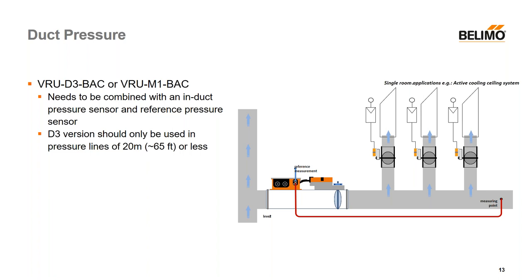A nice thing about duct pressure control is that if you have a corridor with many identical or similar rooms downstream, controlling the pressure of the duct means you don't necessarily have to measure the flow at each terminal unit — you've essentially eliminated the pressure dependency of the system because you know the duct pressure is going to be constant. One last note: if you're doing this with the D3 version, make sure the pressure lines are less than 65 feet, because you could have pressure drops over that distance. For longer runs, we prefer to use the M1.